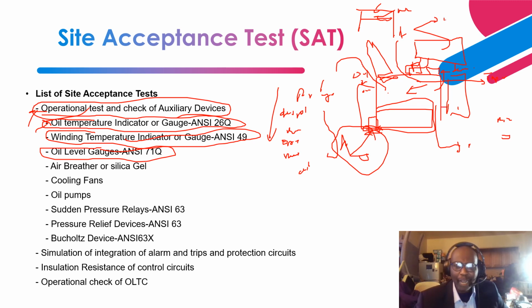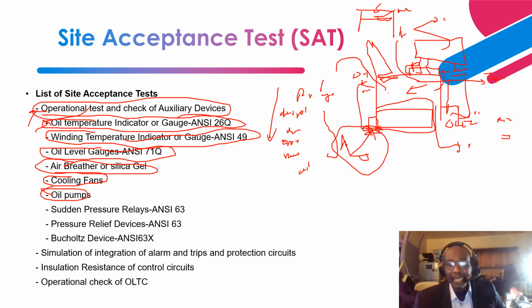And if you have a radiator, if you have an OLTC, we also have an oil level gauge in the OLTC. Next is the air breather silica gel, which is for the free breathing. Then the cooling fans and the oil pumps. Some of the transformers, based on the size of the transformer, use oil pumps. Then the sudden pressure relays, right?